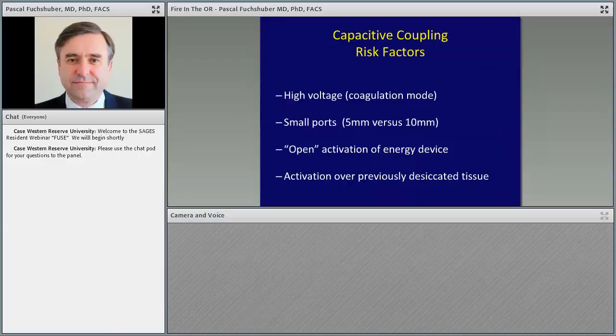So the risk factors, I'm repeating myself: high voltage, so coagulation mode, small ports, open activation of energy devices, which means you don't wait till the device touches the tissue, you activate before, and the ESU automatically tries to overcome that resistance, which is the air, and jumps the voltage up. And then you get arcing and high voltage built up in the instrument before it discharges into the tissue. So don't do that. Always try to touch the tissue before you activate.